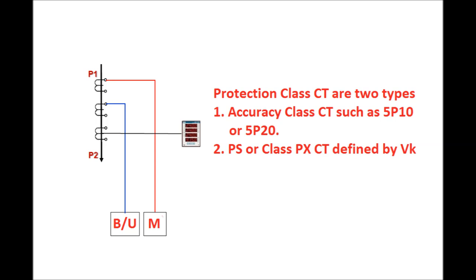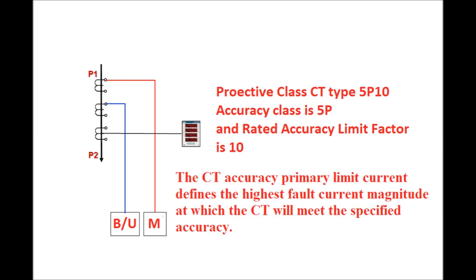For a 5P20 class CT, if 20 times the rated current flows in the primary side, then the maximum error will be 5%. Another type of CT is the Class PX CT, which is defined by the knee point voltage of the CT. In the case of protection class CT such as 5P10, the 5 is the accuracy class and 10 is the accuracy limit factor — that is, the maximum accuracy primary limit current under rated burden on the secondary side of the CT.